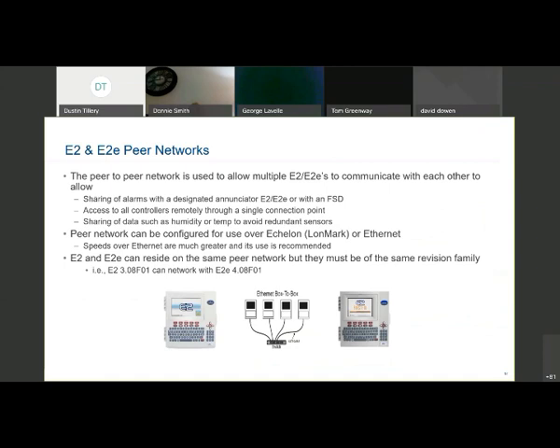All right, so let's talk about peer networks. The peer-to-peer network is used to allow multiple E2s to communicate with each other. So if you have a store that has 4 E2 controllers, and they're all tied into the same server, with a couple of changes in the peer network settings, we can have all of those controllers talking to each other on that same network. Useful for sharing data or sharing the alarms. If we have an alarm from the rack, it gets sent down to our building controller, which then allows it to call out to the server to alert the manager or somebody up at the store that they have a problem.